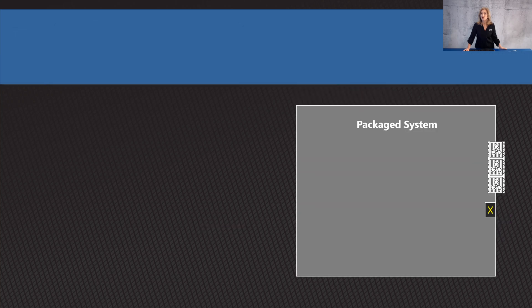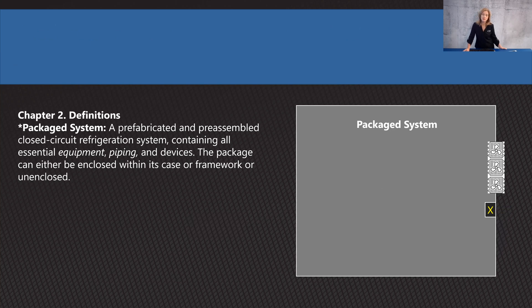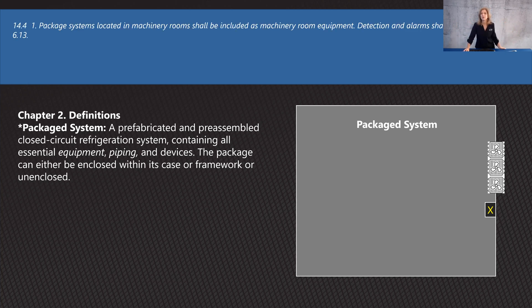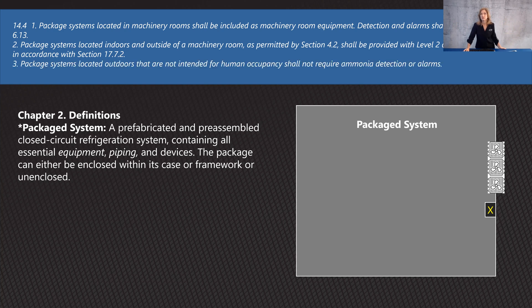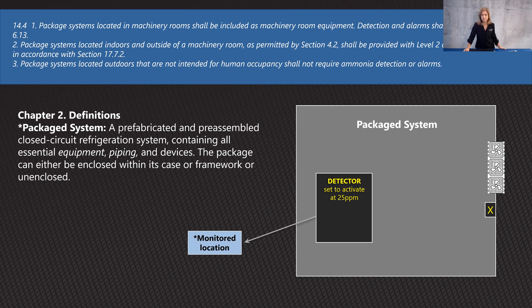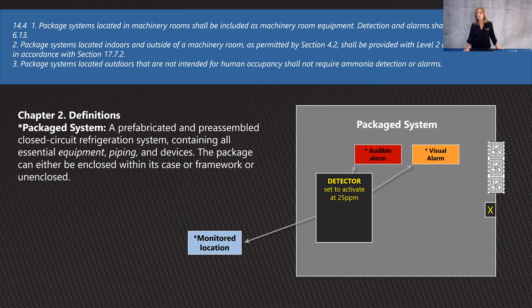Package systems are becoming more and more common. These are prefabricated, preassembled, closed-circuit refrigeration systems containing all the essential equipment, piping, and devices — enclosed within a case or framework, or unenclosed. They're often delivered on a trailer and placed on a rooftop. If all the equipment is exposed and outdoors, you don't need detection. But if there's any chance people will go inside the enclosure, you have to have a detector and audio/visual alarms.